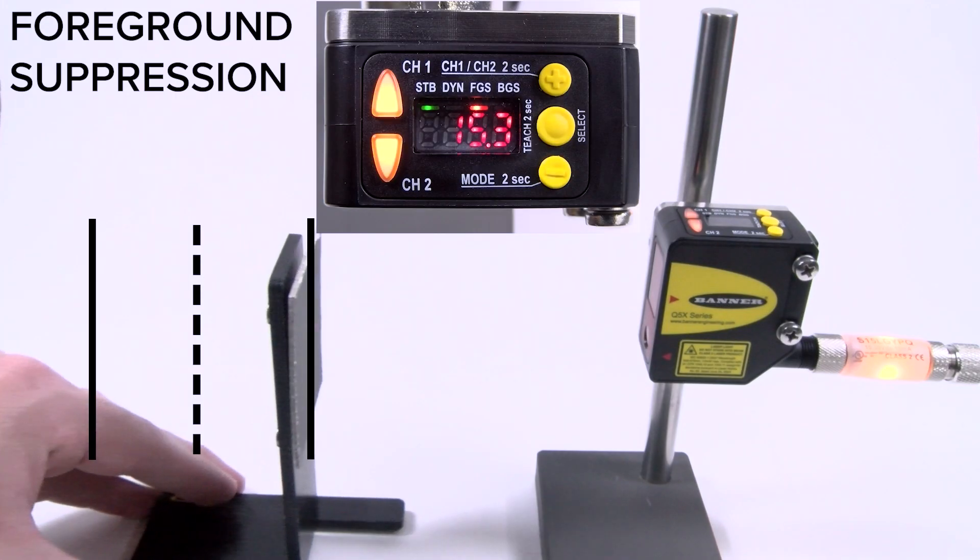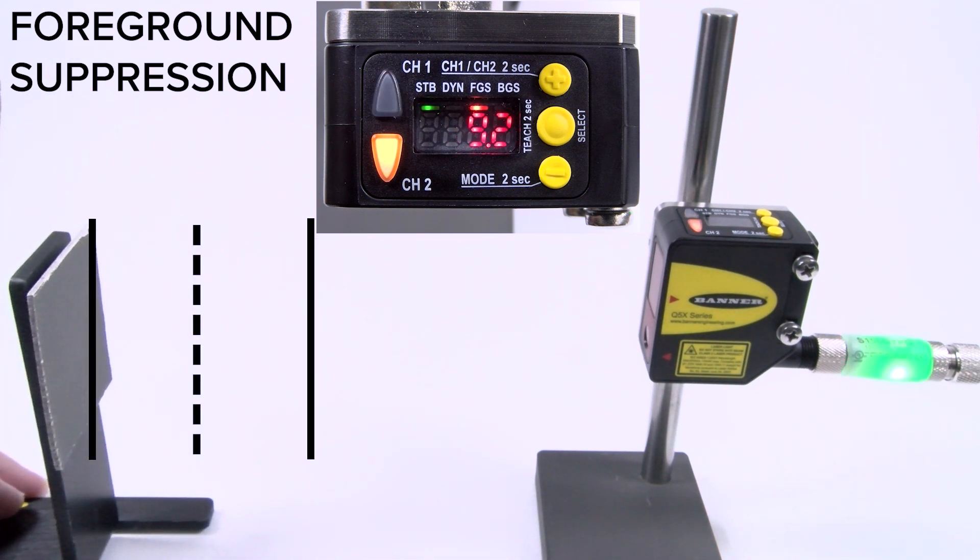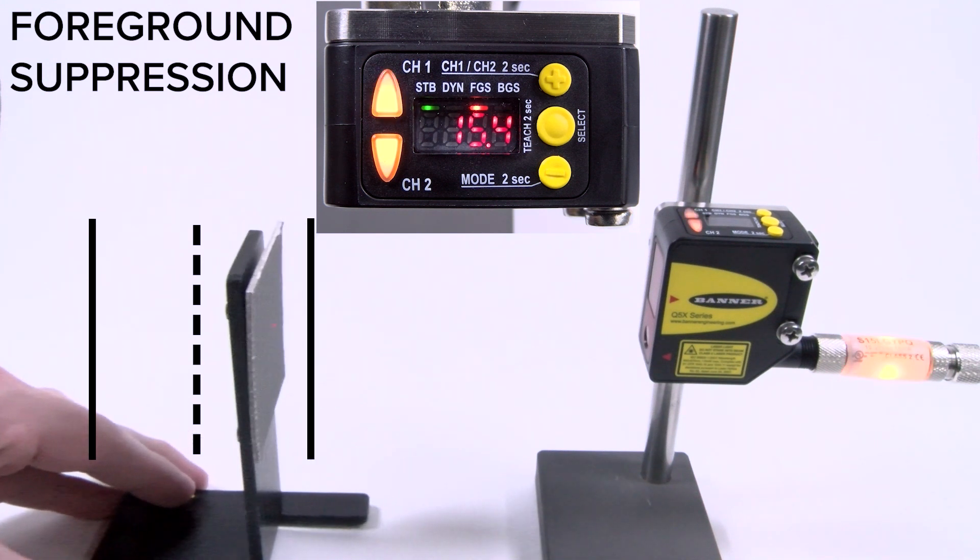Foreground suppression is best used when you want to keep an object in a constrained area. The sensor sets a window around the taught point, then anything in front of or behind the window will be ignored.